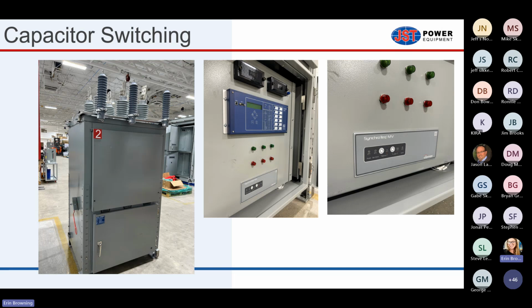That's a standard device. The zero crossing relay specializes in monitoring when the voltage is zero across each of the phases. And because we have 3 phases that are each individually controlled, we can actually monitor 0 volts on each phase. As you guys know, the current and voltage don't cross zero at the same time across all 3 phases, right? They're 120 degrees apart from each other. So in a traditional breaker, that's a 3 phase operating breaker like ABB or Siemens, if a customer is trying to do zero crossing to minimize transients or inrush current across their vacuum bottle contacts, they're really only doing zero cross on one of the phases. The other 2 phases are 120 degrees out of phase, so they're absolutely not at zero crossing. So you still have this transient phenomenon happening on 2 of the phases.